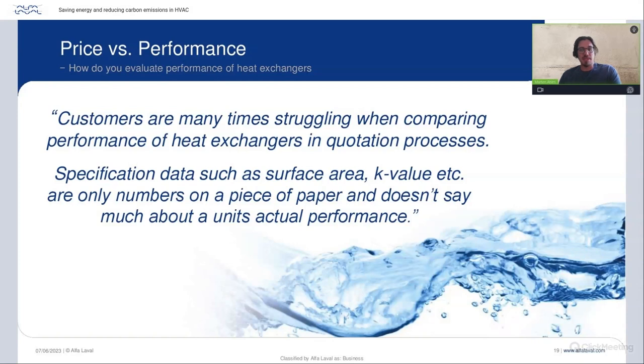And most commonly, the data that is used from specification sheets from the equipment to validate that you have received the same performance from different manufacturers is the surface area when we talk about plate heat exchangers. That is something we see more or less everywhere. But if you don't know technology in heat transfer equipment, such as plate heat exchangers, it's extremely hard to tell if the data you get in the tech spec is actually accurate enough. I've been supporting, I don't talk about hundreds, I would more or less say thousands of projects now. And unfortunately, it is very true. We see this trend everywhere. Surface area is the major factor that is being compared. But in reality, the data you find in the technical specification from any manufacturer cannot be trusted, unfortunately.